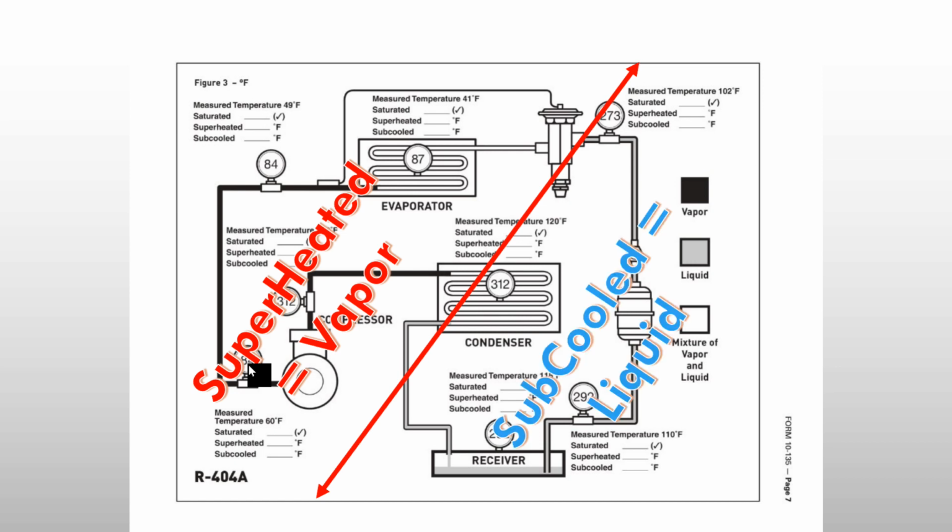The other thing on this diagram is subcooled liquid. That's after it comes out of the condenser, turned back into a liquid. And sometimes we have to add subcoolers to systems to bring it down even further. So sometimes the condenser can only condense it, but then there's other refrigeration devices such as plate and frame heat exchangers that allow us to subcool it even more.